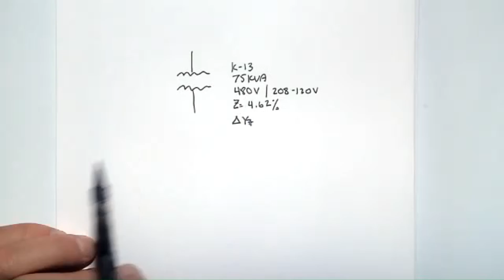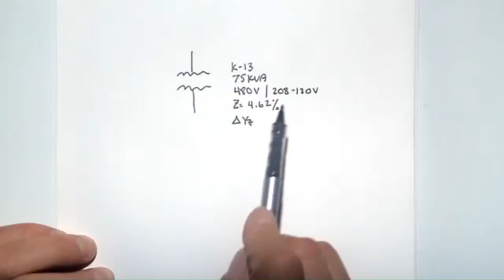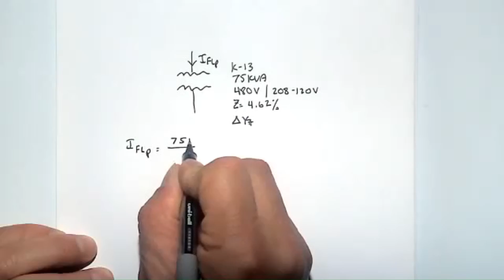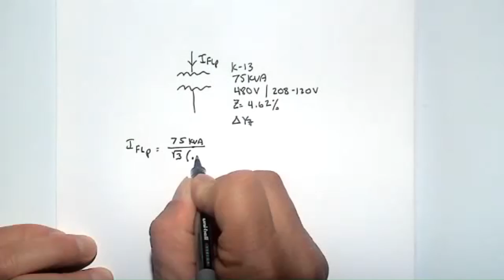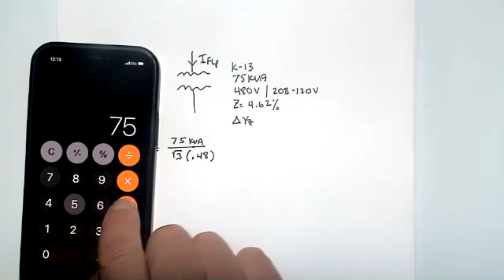480 volt, 208, 120. What does that mean? It's 480 line to line delta on the primary, 208 line to line on the secondary, connected in a Y, so 120 line to neutral. And the impedance is 4.62%. So let's calculate I full load primary. All right, so we go back to our equation we had before. I full load primary, in this case again 75 kVA, is kVA divided by the square root of 3 divided by kV. And again, we have to make sure we use 0.48 here. So we take 75 divided by 1.73 divided by 0.48, and we get 90 amps.